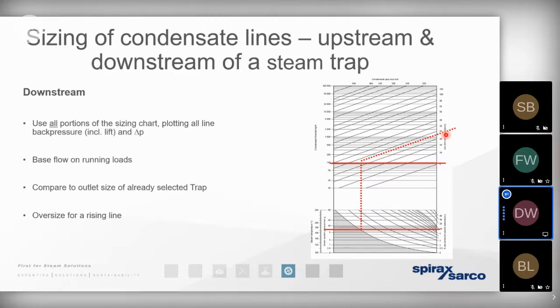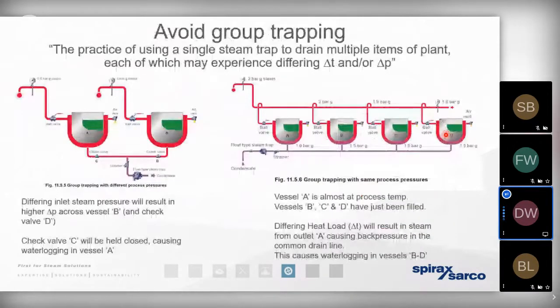But please, whenever there's a fall in pressure of the condensate, bear in mind there will be that expansion to contend with. So for that reason, we strongly encourage you to ensure that each individual process has its own dedicated steam trap. That's because processes are going to work at different rates, different temperatures, pressures and mass flow rates. So not only is there a different mass of condensate to remove across the trap, the flash steam, that volumetric increase, is also going to be present at a different rate. And any flash steam that occurs, with that huge expansion of volume, can create a significant back pressure on the trap.